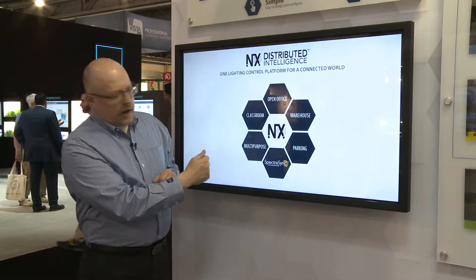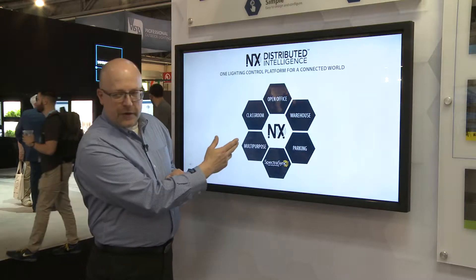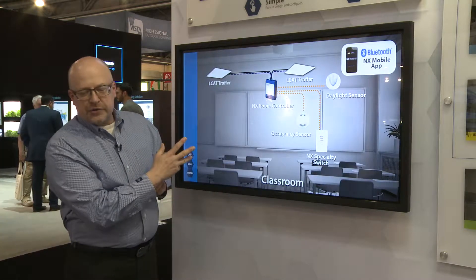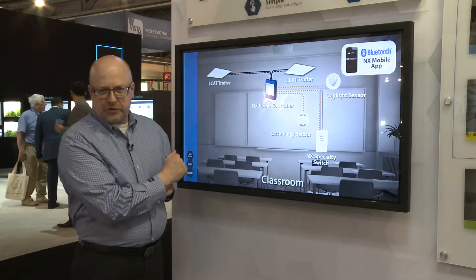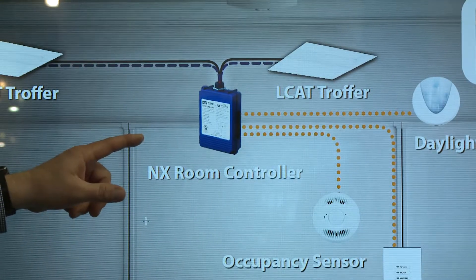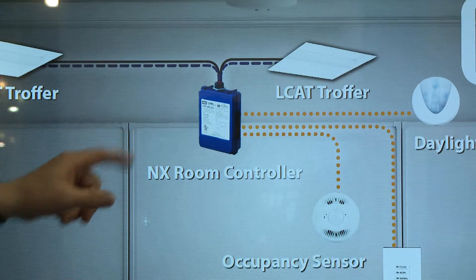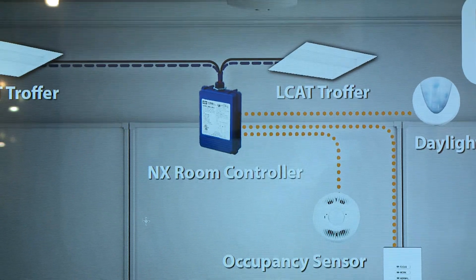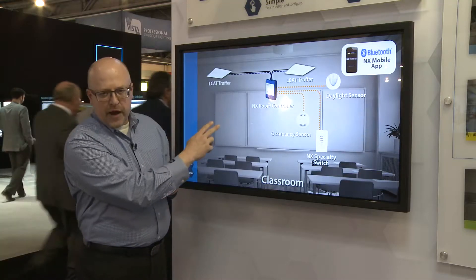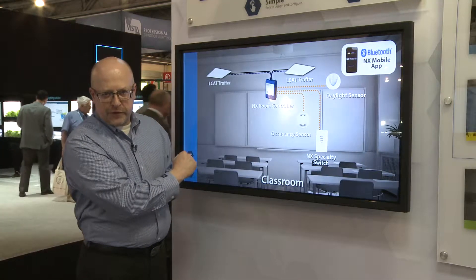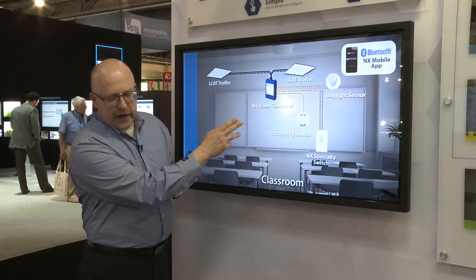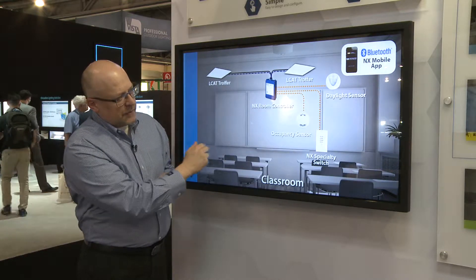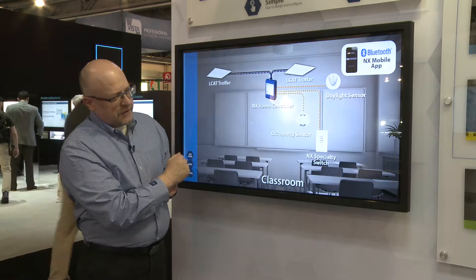If I step back and look at other examples, for instance like a classroom, I'm able to then use the NX room control solution style where I've got an NX room controller having two relays and two 0-10 dimming lines that allow me to connect to a variety of different fixtures and also allow me to plug in other controls like a daylight sensor or a room-based occupancy sensor.